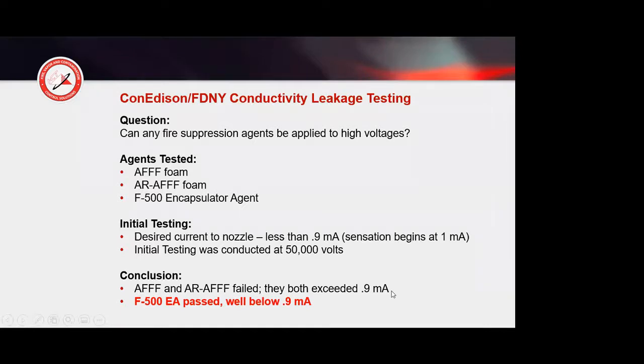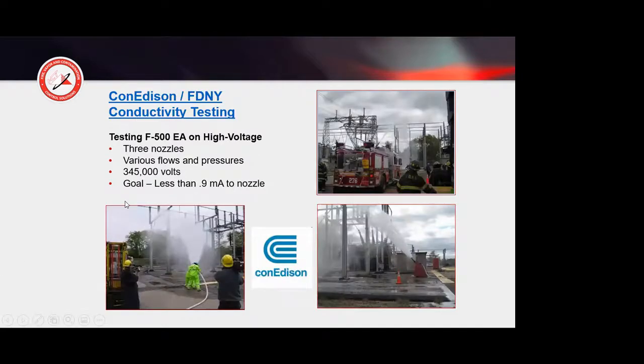So what does it mean? It means that if you take foam and you apply it in an energized environment, because you have bubble-to-bubble interaction, you will get a current feedback to the nozzle, which can be very dangerous to the firefighter. But with the F500, they achieved very good results, which then said, hey, let us go ahead and look at F500 through 3 different nozzles with various flows and pressures at 345,000 volts. Our goal is less than 0.9. Let's see what happens.